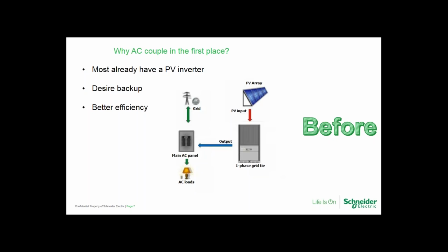So many customers, when they're interested in AC coupling, if they already have a grid tie inverter, probably are going to want to know what the differences in efficiency are, and that is one of the main considerations that I hear for the most part: installers believing that AC coupling is the more efficient way to go, and it can be. It certainly can be. That does require that certain other conditions are true, though. So when you're AC coupling, the PV power must occur when the load demand is present to get the maximum efficiency.